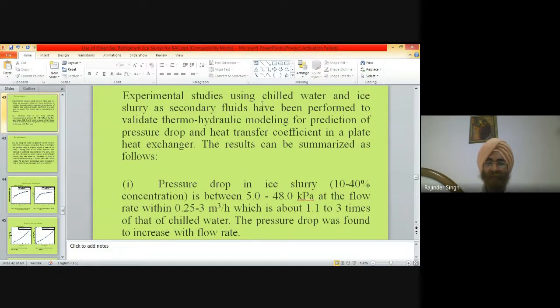Using chilled water and ice slurry as secondary fluid, performance was validated by thermohydraulic modeling for prediction of pressure drop and heat transfer coefficient in the plate heat exchanger. This is our result. The pressure drop of the ice slurry at 10 to 40% concentration is between 5 and 48 kilopascal at a flow rate of 0.25 to 3 cubic meters per hour, which is about 1.1 to 3 times that of chilled water. The pressure drop was found to increase with the flow rate.